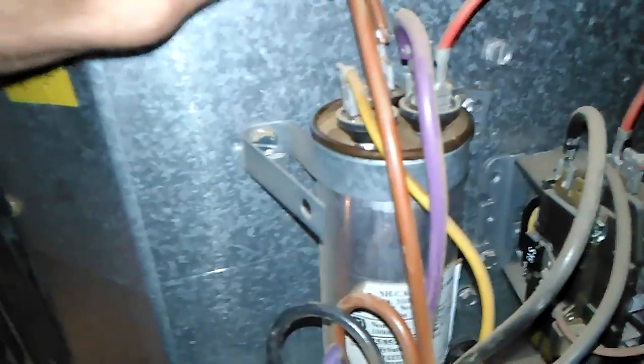But I am going to keep my dual capacitor in here which runs both the condenser and the fan, but I am going to bypass that by taking the brown fan side off. And I will just put my single capacitor in here because the other side of the capacitor is still working.